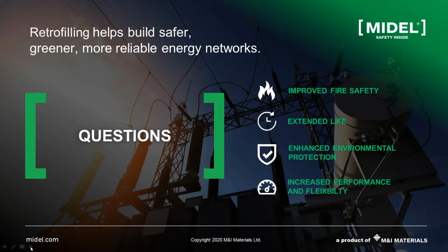Yes, thank you, Matthew. I told you that below 33 kV, we haven't seen any issue with the construction of the transformer, like a distribution transformer. So up to 33 kV, everything looks fine from a technical point of view. Above this, up to 69 kV as you mentioned, many times it's okay, but a couple of times you need to check some extra things, like the on-load tap changers, or checking the bushings and other accessories. So yes, many times it's capable up to 69 kV, but it's much better if we have a conversation about it, and later we can decide together.